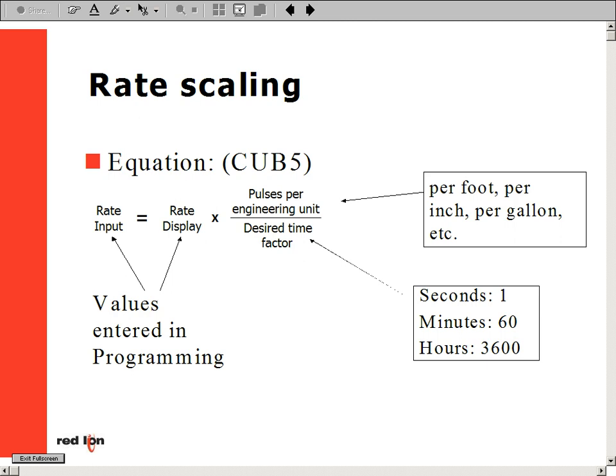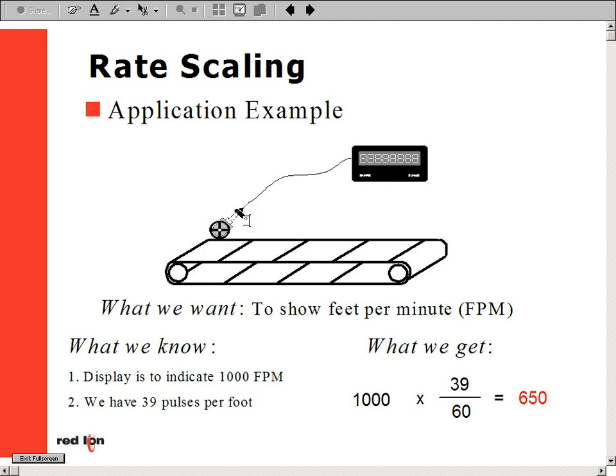Our example needs to display feet per minute of a process. Our fastest rated speed is 1000 feet per minute, and 39 pulses per foot are given off from our sensor. Our rate input then becomes 1000 times 39 over 60, or 650. We would then enter in the programming 1000 for a display and 650 for an input.